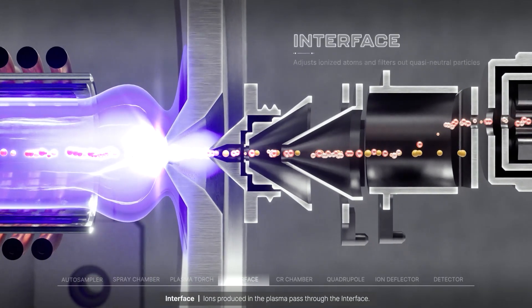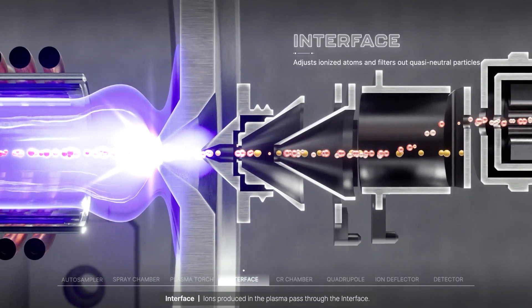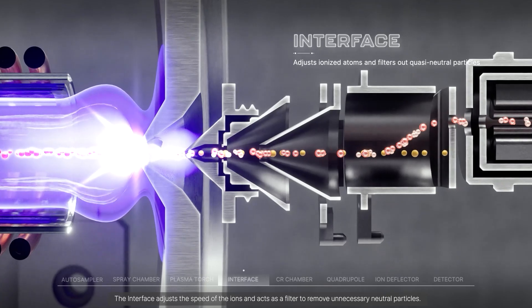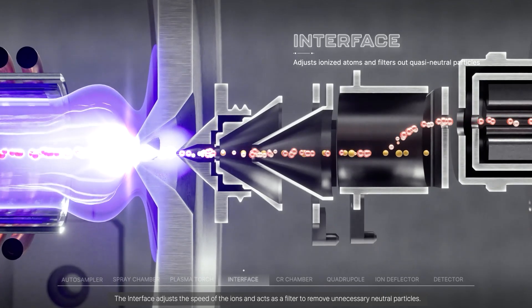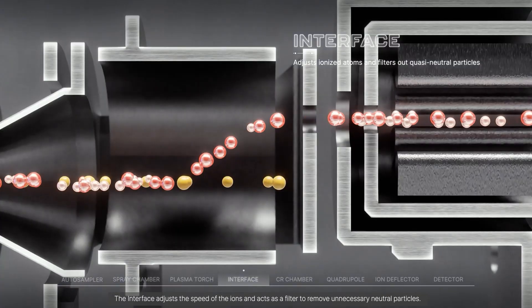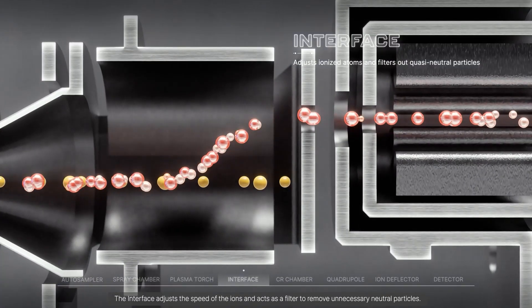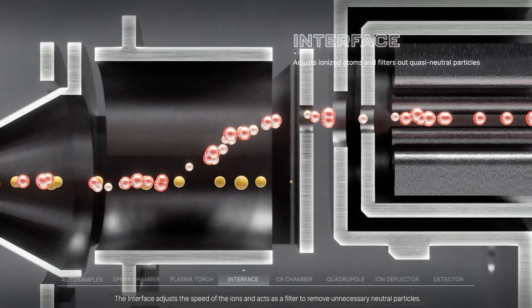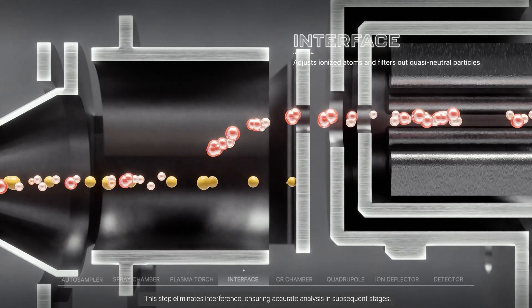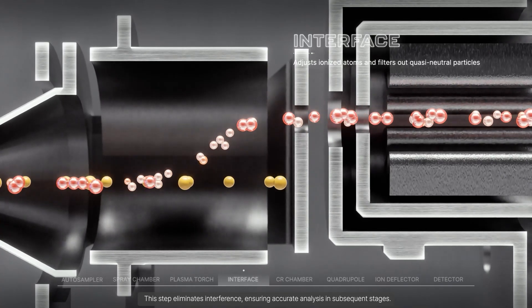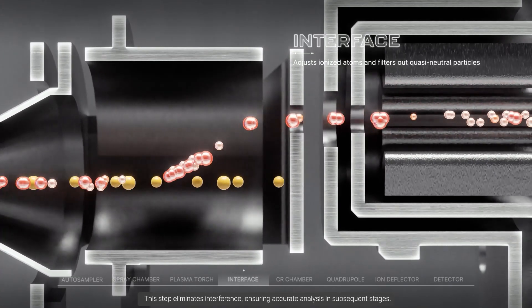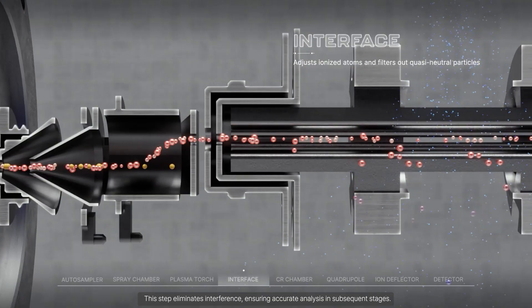Ions produced in the plasma pass through the interface. The interface adjusts the speed of the ions and acts as a filter to remove unnecessary neutral particles. This step eliminates interference, ensuring accurate analysis in subsequent stages.